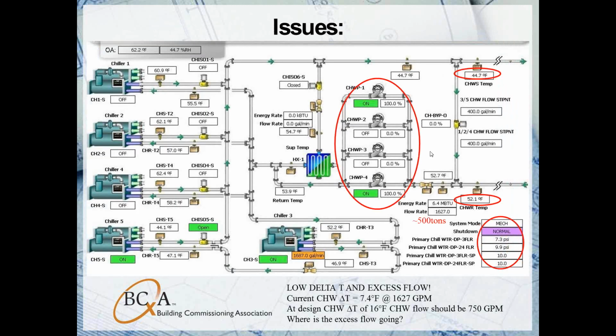So, jumping into the retro commissioning project itself, what you're looking at right now is the Niagara graphic of the chilled water plant, and there are some fairly obvious issues right off the bat that you can see in this picture here. We've got excessive chilled water pumping.